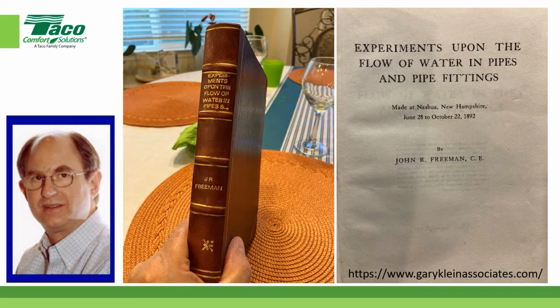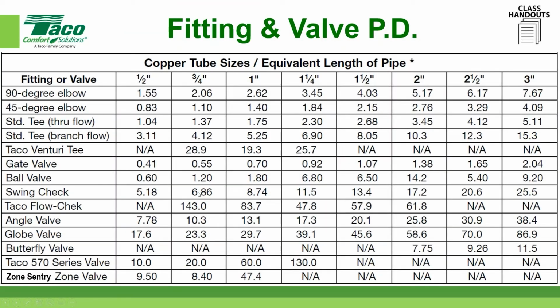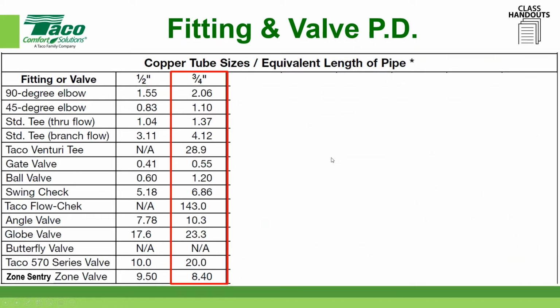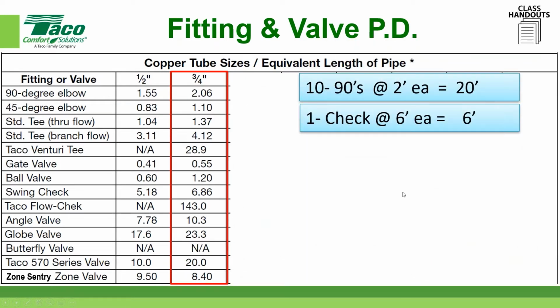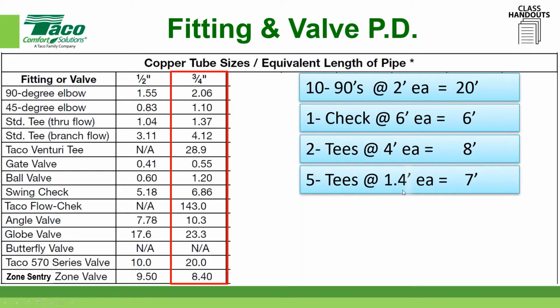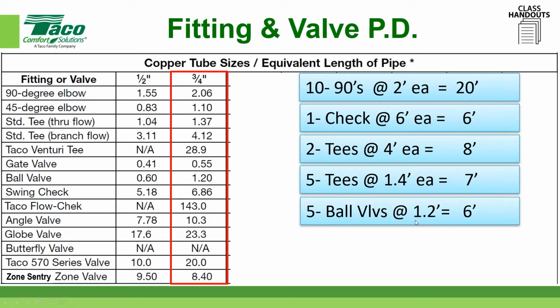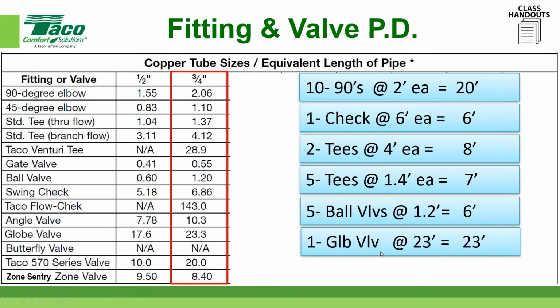I'm just giving you a little background on where these equivalency charts come from, like I'm showing you now. Okay, so we're going to go with a 3/4 inch based on the flow that we were using, which was 3 gallons a minute. And so we're going to shade all this out, and we just start tallying things up. We just start counting things: check valves, T's, T's on the branch, T's on the run, etc. Ball valves, globe valves, anything that was in there should have been some zone valves, etc.